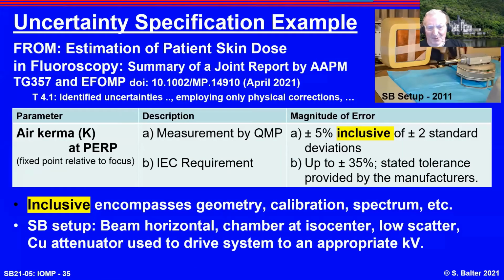Here's an example. This is brand new, an AAPM EFOMP report on calculating patient skin dose based on references. They give a very extensive table of uncertainties. I've looked at the air kerma at the reference point measured by the medical physicist. This standard requires 5% inclusive with a coverage factor of 2. This is a fairly tight specification.